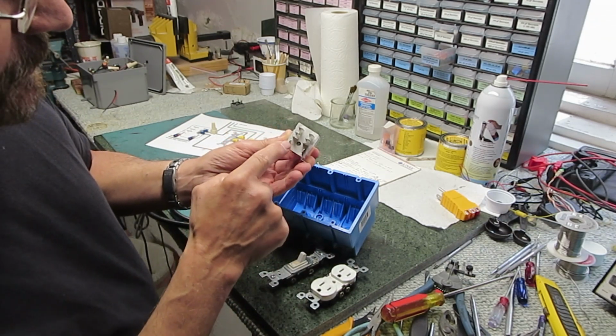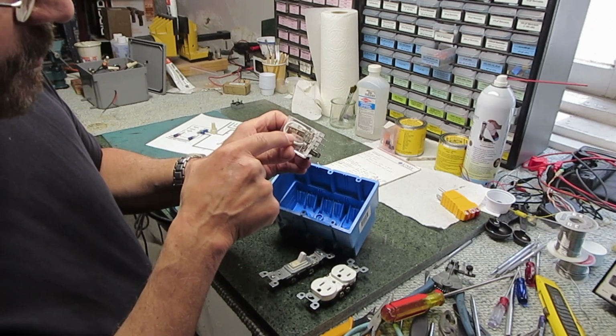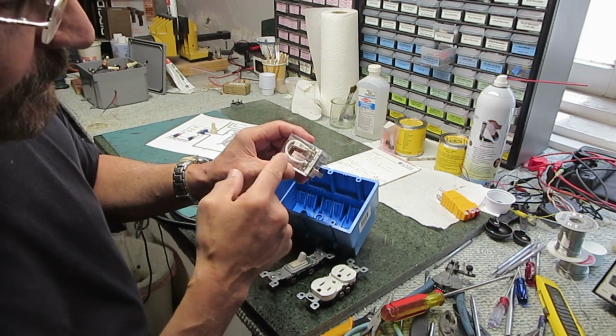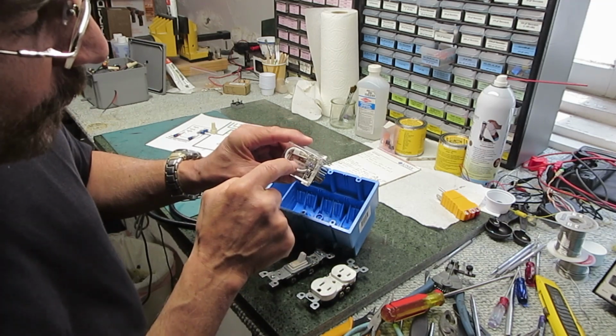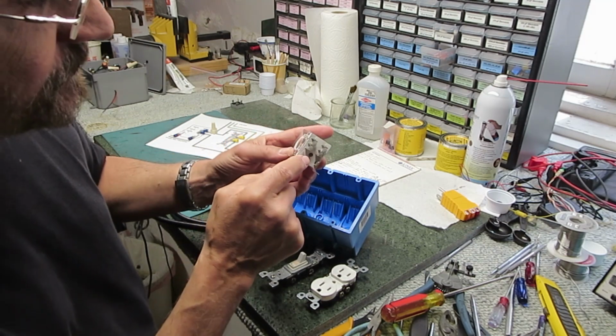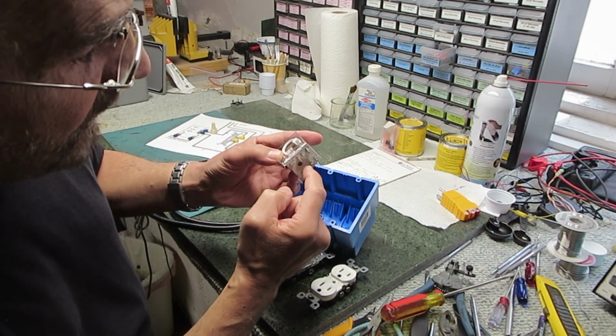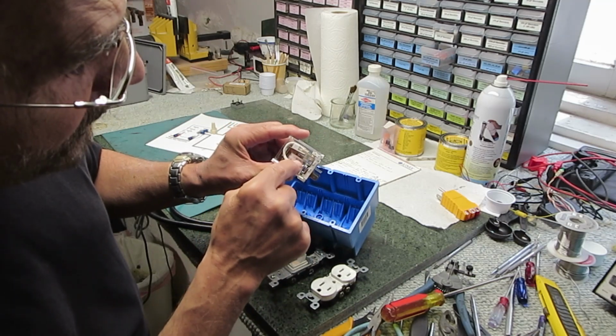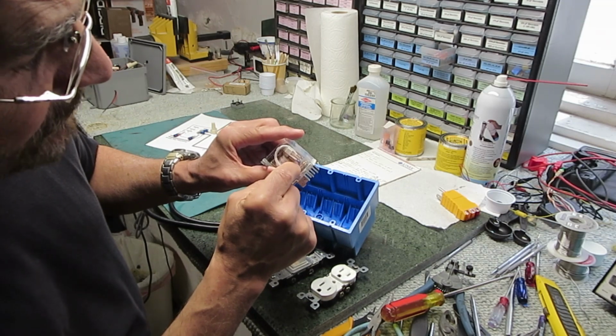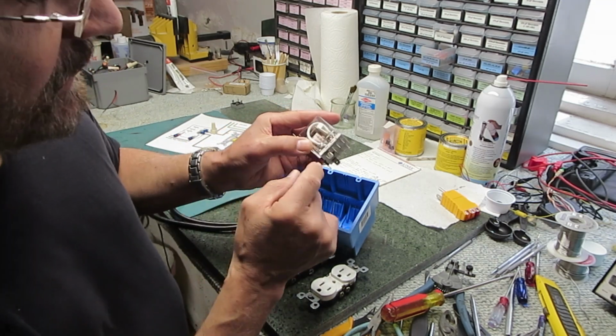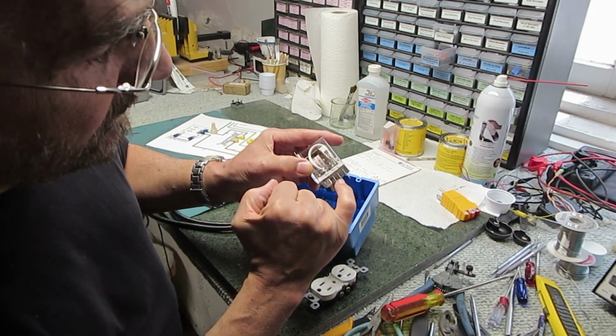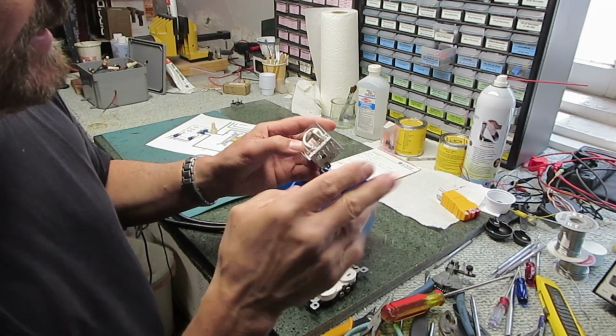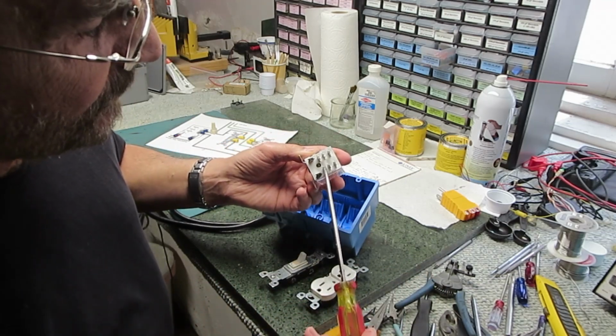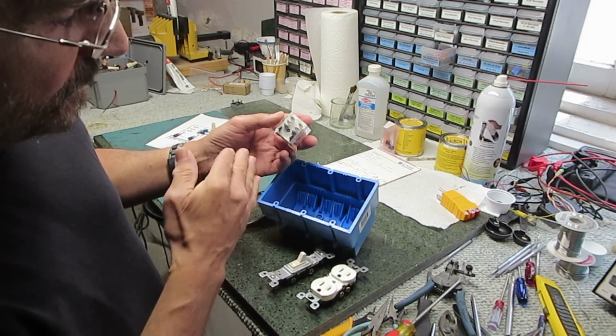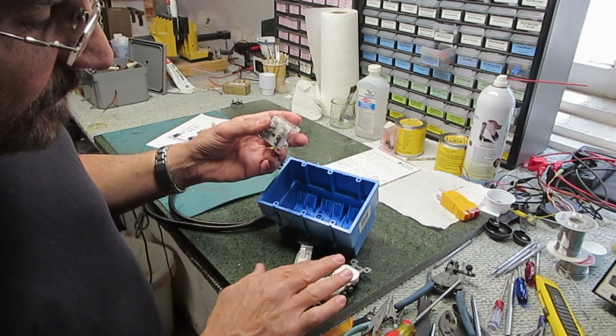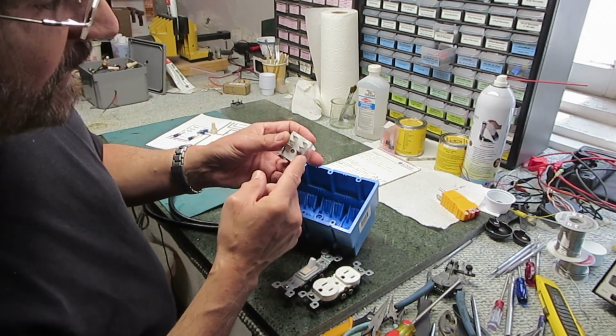These 2 are the low voltage tabs that go right to the coil. It's kind of cool that you can see inside here. You know exactly where all the connections go. So these two energize the coil, and it says right on it, DC 12 volts. This tab and this tab is your common. It's connected to that white wire. And these two are connected to the switch, the part that goes up and down. This tab is, well, that's not important. Anyway, we're going to use these two tabs, number 6 and number 4, just because it's toward the switch and the receptacle, and it'll be easier to use.